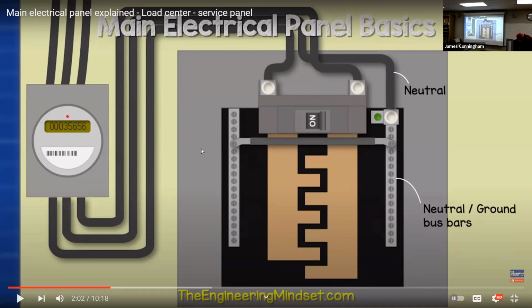In your main panel, see this little doodad here? This has to be connected to the ground bus bar and the neutral bus bar, so that the ground bus bar over here and the neutral bus bar over here are connected together. In case there's a short and it hits a neutral wire, we want that neutral wire to be able to get to the ground bar. So a lot of the old panels didn't have a separate grounding bar. You would see the white wires and the ground wires all on the same bar. It's basically going to the same place, just returning the electricity.